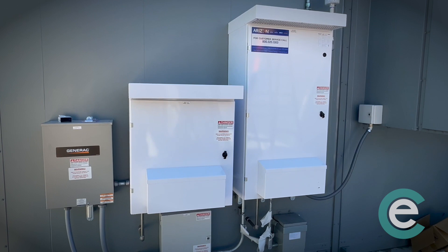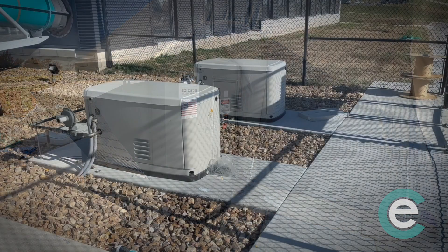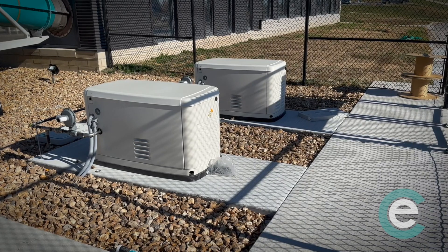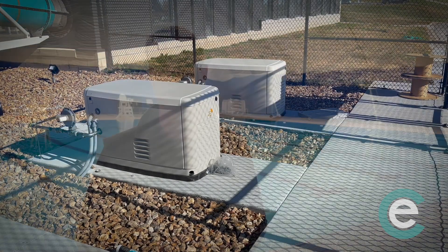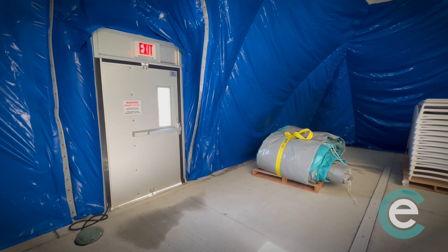If the primary generator needs support, we have a secondary generator that is also electric and natural gas that would assist in the event of a storm. If we do lose both electricity and natural gas — which I don't think we would, but if we did — we have two other onsite generators that would also be able to push heat and air into the dome to keep it inflated. If all of those go down, it is 25 minutes to exit the dome and we have three exits inside that we will be able to get everyone out safely.